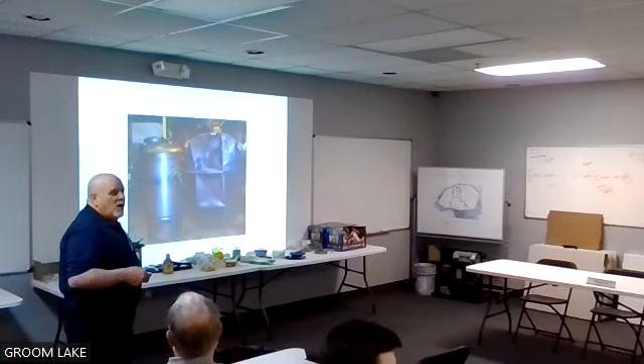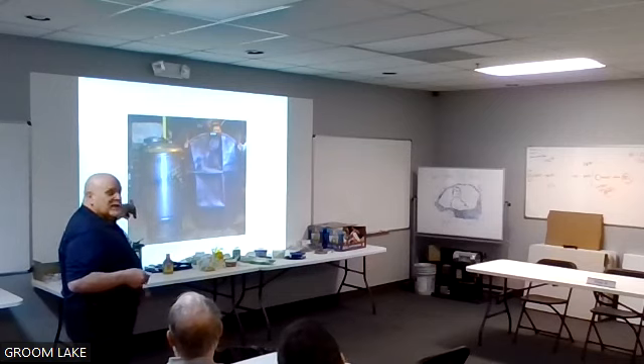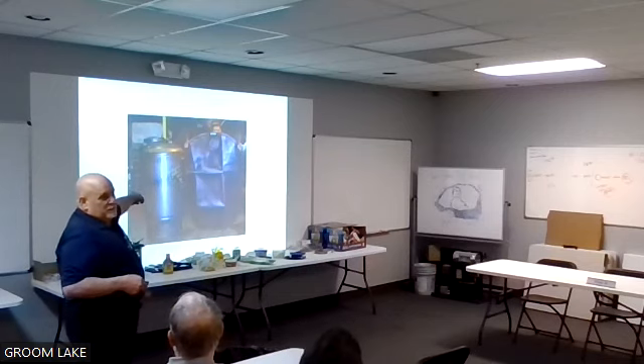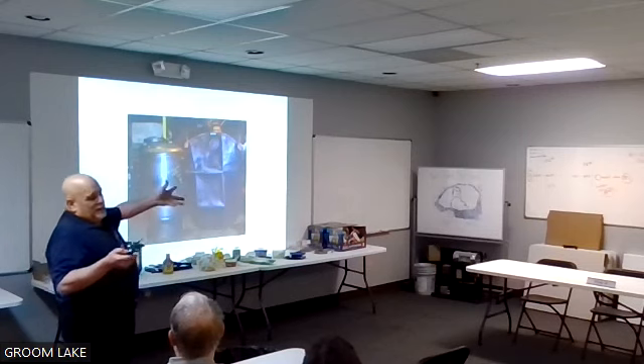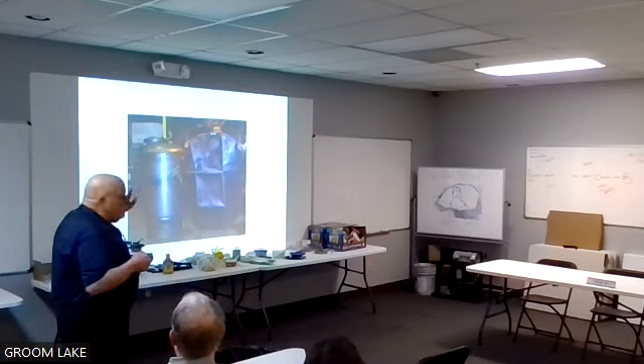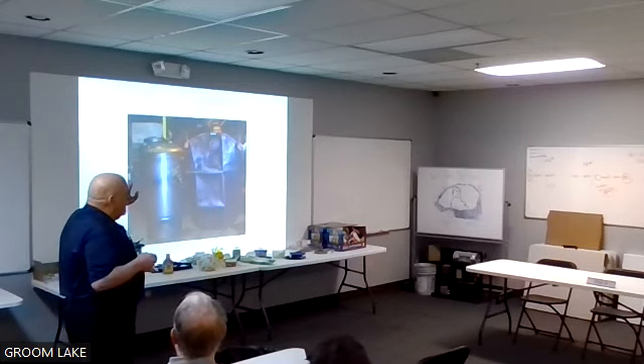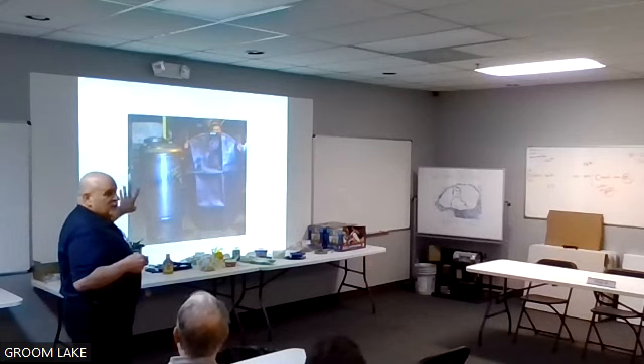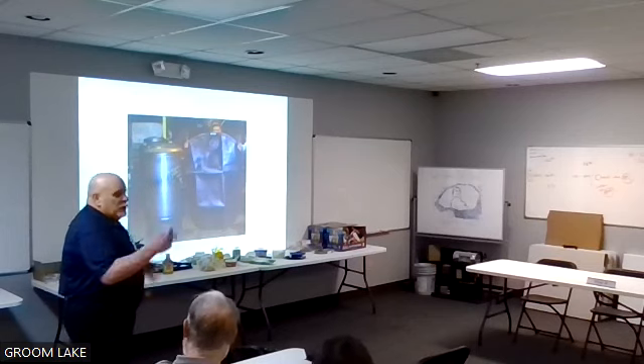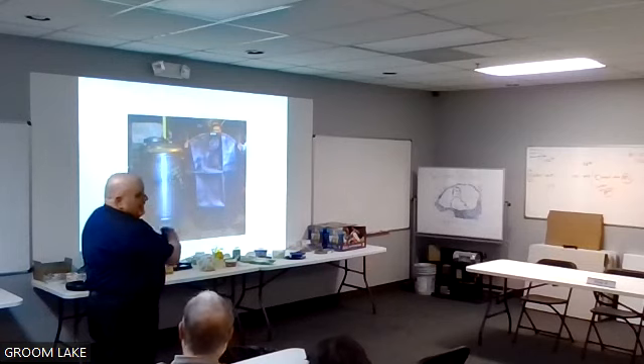You said 100%, there's other things. If I have a 100-gallon tank, I can put 100 gallons of water in this. So where's the air go? Well, you don't want that. I'm just saying, you have 100% acceptance. When you do the calculations, it'll say I'm only having 30 gallons of acceptance, I need a 100-gallon tank.